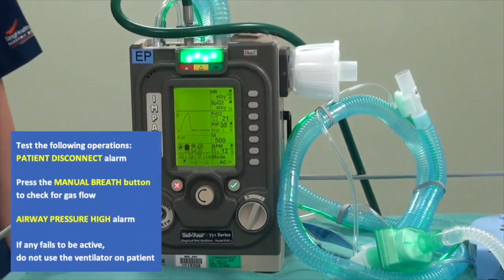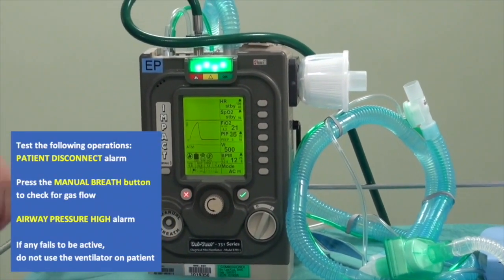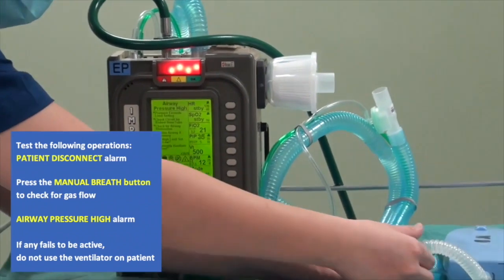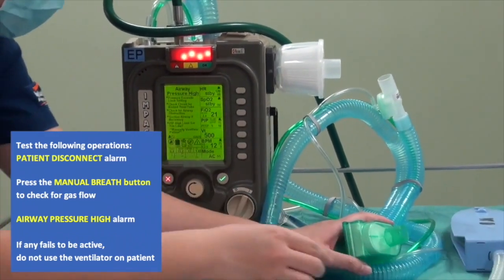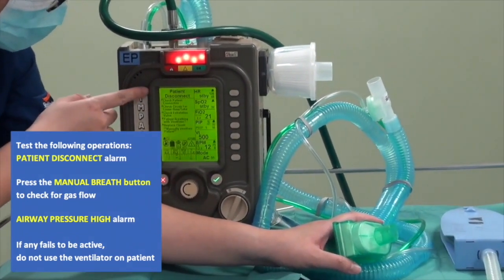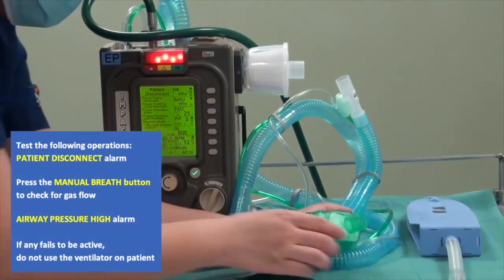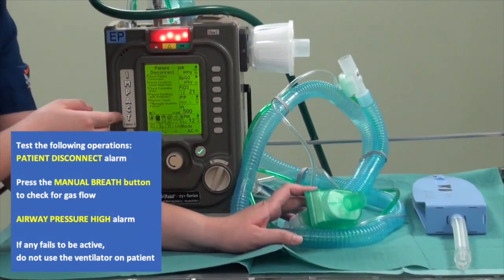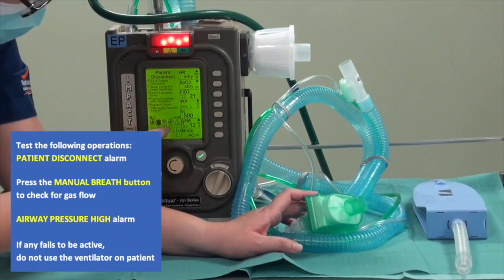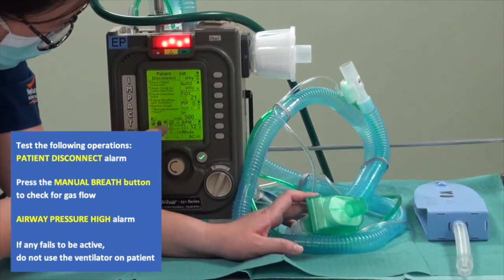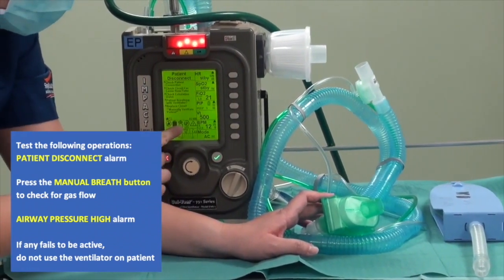The first alarm that I need to test is the patient disconnect alarm. When I disconnect it from the test lung, the patient disconnect alarm should come on. There are no audio alarm now because it's within my first 2 minutes when there's an alarm silence. There are 11 seconds left to the alarm silence right now.